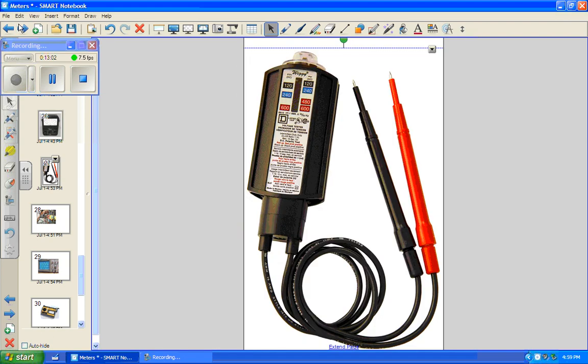This is the Wiggy voltage tester — there's a little solenoid that pops up at the very top. Be very careful where you point this when measuring voltage, just in case you happen to read 4,180 instead of 480. Also, if you do measure 4,180 volts, there'll be a ball of flame from the arc flash that will burn every piece of exposed skin — and it will be obvious years later whether you had your gloves, safety glasses, and hard hat on.